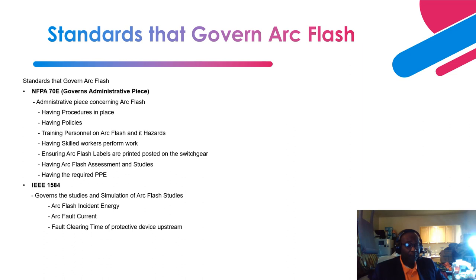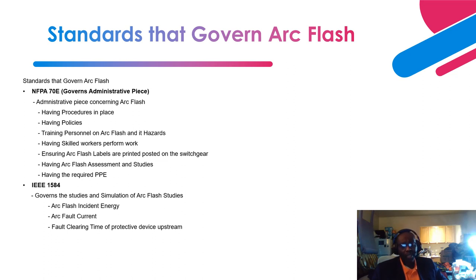Next is IEEE 1584. This standard governs the studies and simulation of Arc Flash. It covers incident energy calculation — calculating incident energy in calories per square centimeter. The key parameters needed include the arc fault current, the short circuit current, and the fault clearing time of the upstream protective device. For example, a typical upstream protective device for a switchgear is the incomer protective relay that operates the incomer breaker.